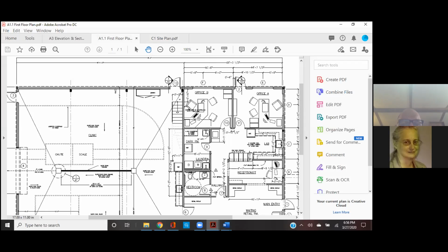Yeah, just sketch out how you would supply that, where they'd go. Oh, okay. So would that split off of the main water line I have coming in? Don't put it on that plumbing drawing. Do a separate drawing, because it's going to be a separate system. You don't want to take a chance that you contaminate drinking water with that system. It should be a closed system. So it has to have its own main water line? No, it'll come off the main water line.